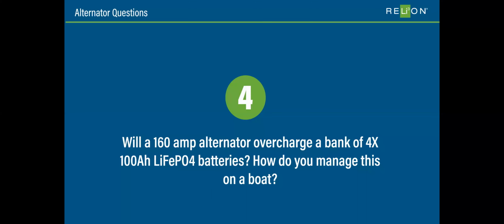Now that you have 4, that current tends to get spread out over those 4 somewhat evenly. There is some imbalance in the current share, but roughly each battery is going to see about 40 to 50 amps of that 160. So it's going to be okay, well beneath the 100 amp max of each single battery. So in this case, it's likely going to be okay.